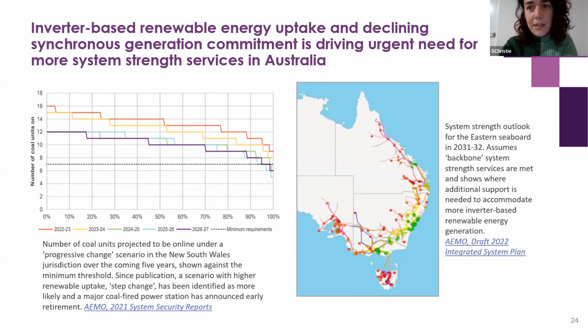For example, synchronous condensers are there to contribute a fault level injection, but also to keep the voltage waveform stable. We spend a lot of time trying to distinguish between those two parts of how we explain system strength, because we want to make sure that over time, new solutions which are not just synchronous condensers can try to contribute to keeping that voltage waveform stable.